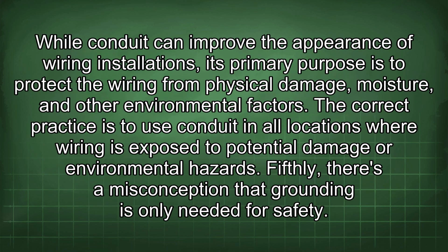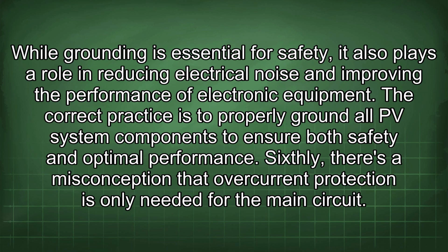While conduit can improve the appearance of wiring installations, its primary purpose is to protect the wiring from physical damage, moisture, and other environmental factors. The correct practice is to use conduit in all locations where wiring is exposed to potential damage or environmental hazards. Fifthly, there is a misconception that grounding is only needed for safety. While grounding is essential for safety, it also plays a role in reducing electrical noise and improving the performance of electronic equipment. The correct practice is to properly ground all PV system components to ensure both safety and optimal performance.